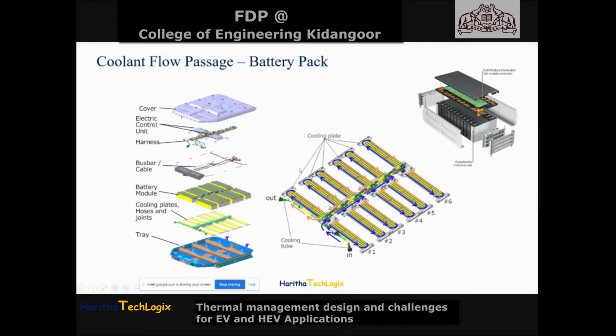Basically this is the cooling plate, mounted at the bottom side, below the module. The modules will be placed on top of this cooling plate, but not directly. Instead, between the cooling plate and the module, there will be a thermal management paste or adhesive that will improve the heat transfer from the module to the cooling loop.